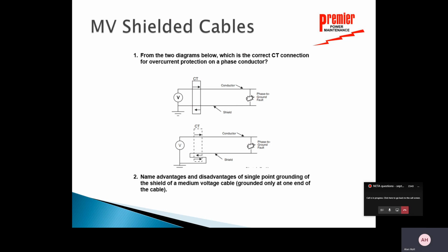Medium voltage shielded cables. From the two diagrams below, which is the correct CT connection for overcurrent protection on a phase conductor? So I've got a single phase conductor here, and I'm looking at a potential ground fault right here. There's my shield, and there's my conductor. If I look at the top layout, I've got the conductor going through that CT. I've got fault current coming here, and I've got all that fault current coming back on the shield.